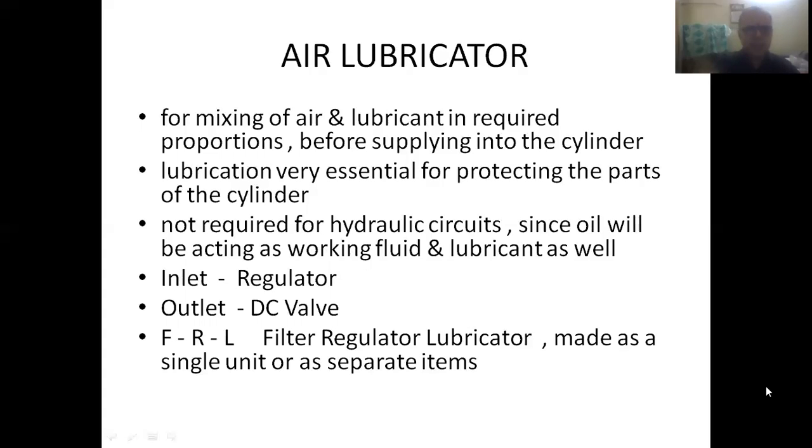Now friends, in the case of hydraulic circuits, oil is used for operating a hydraulic circuit. So this oil will be acting on one hand as a working fluid, and on the other hand, it will also be acting as a lubricating oil or a lubricant. Therefore, a lubricator is not at all essential for operating a hydraulic circuit, but it is very, very essential for operating this pneumatic circuit.